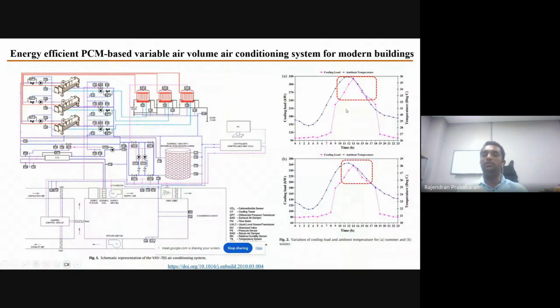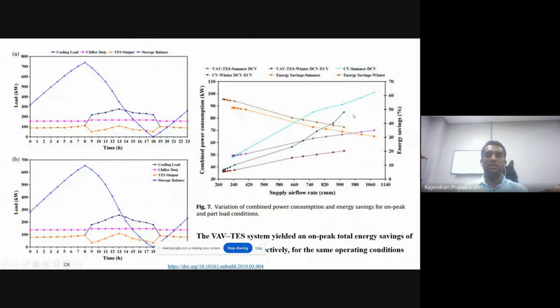So the purpose is to reduce this peak load demand. With this, they introduced a TES to store the available energy when it was not used for the cooling purpose in the spaces. So it will store that cooled energy in the PCM itself, and then that stored cold energy will be delivered during the peak time.